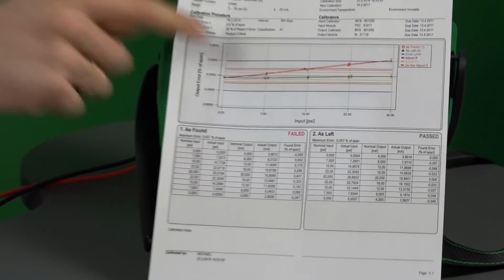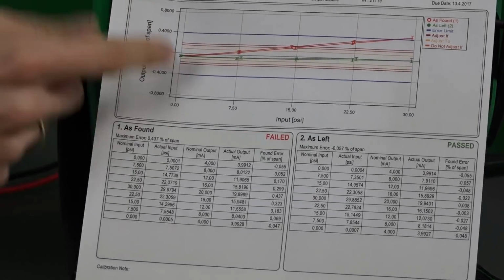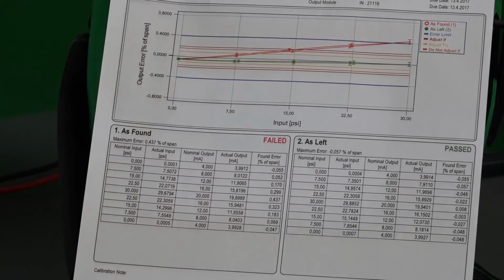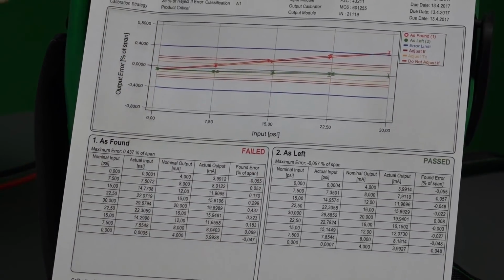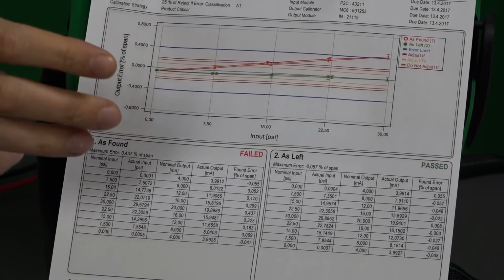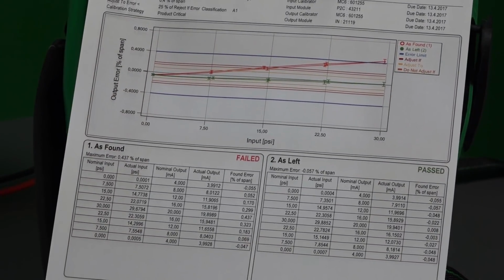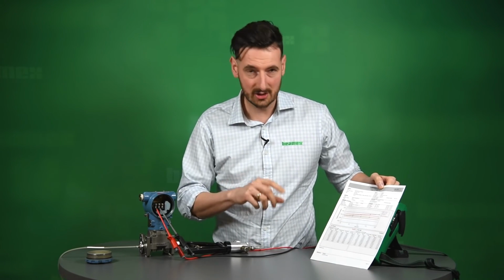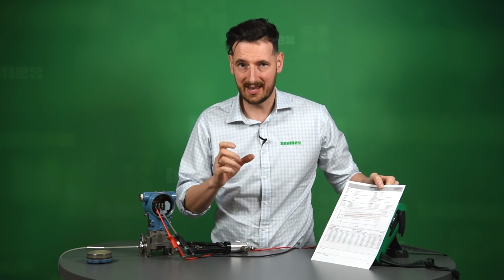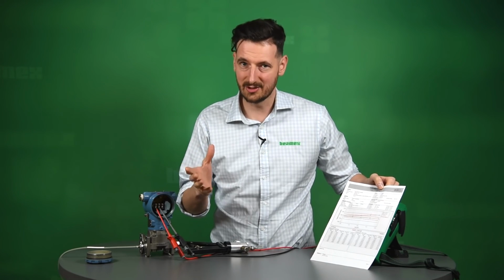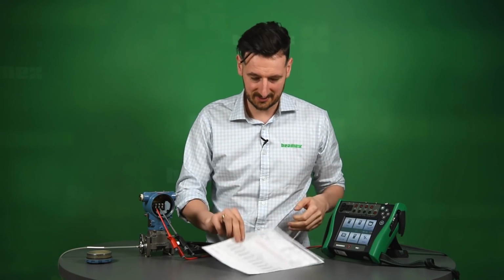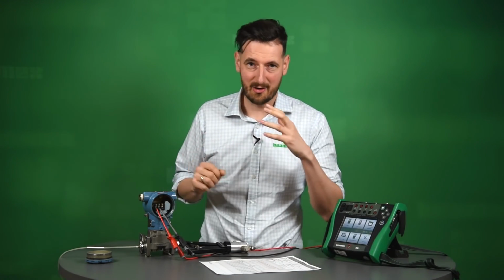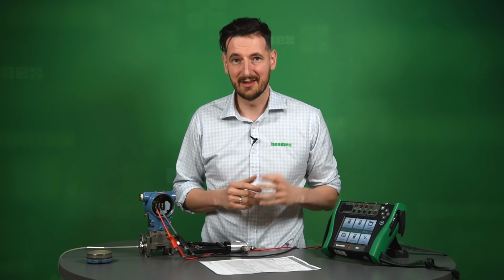You've got the as found failed, as you remember we did. It sort of trended off, you can see here. And then we trimmed it, adjusted, and right now we can see the as left is pass. It's all displayed on a calibration certificate like this. That could be again printed off, put somewhere in the document folders, or just left in the calibration management system. It's up to you, you've got those options. So there you have it. Calibration of differential pressure transmitter HART using documented calibrator. Thank you so much for watching.